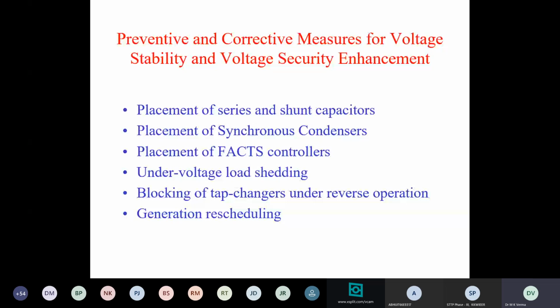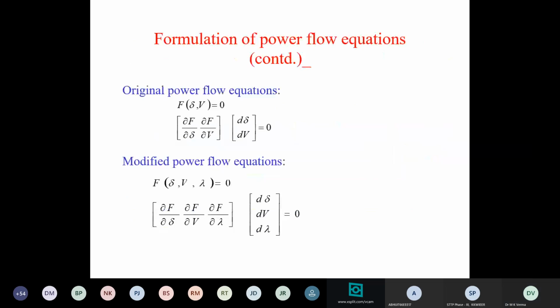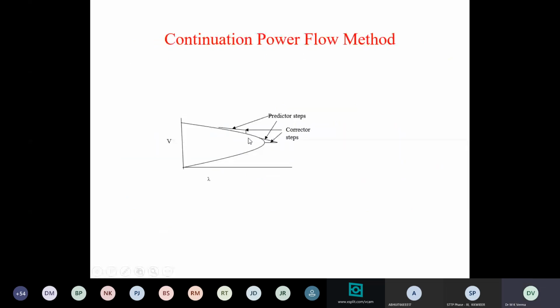Under voltage load shedding: whenever load increases, what do you do to make the system voltage stable? If our operating point is near the nose point, there is a high possibility of voltage instability. But our operating point is here, very far away from the nose point, so the system will remain voltage stable. So you have to operate at light loading conditions. But load is going on increasing, because consumers have to get power, and electrification is increasing day by day. So the system is becoming more stressed, and due to stressed operation, system loading is getting enhanced. So we may operate at this point.